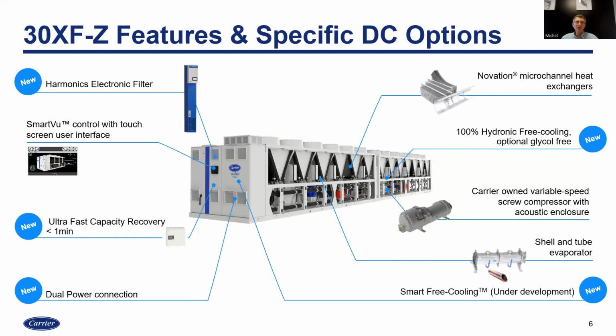During this time the cooling unit stops, but heat is still produced by the data center. So the key is how quickly your chiller can restart and come back to 100%, which reduces the stress on the data center in terms of temperature increase inside the IT space.